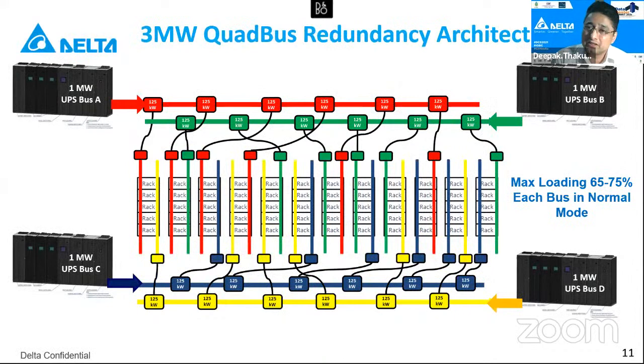Now going ahead, we have customers we are discussing. We have deployed this kind of globally, but in India, I would like to really see this concept, because when you go into mega scale, you also need to look into a new way of redundancy, which is distributed architecture redundancy, where we have a 3 megawatt with a quad bus architecture. Now quad bus is nothing but quad is basically a 4. So we had a tri-bus, which was a 3. Now we have a 4, which is a quad bus. So quad bus means for 3 megawatt, what you need is 1 megawatt into 4 numbers to deliver the same 2N architecture.